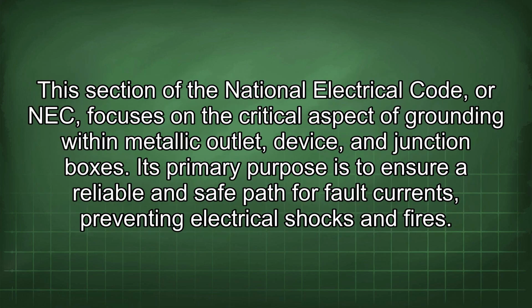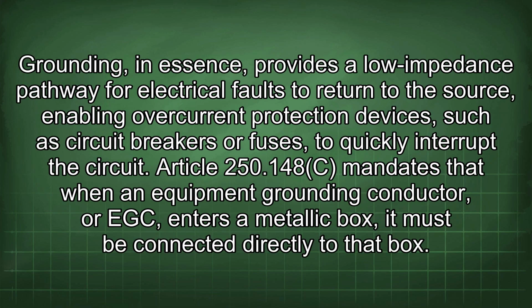250.148c. This section of the National Electrical Code, or NEC, focuses on the critical aspect of grounding within metallic outlet, device, and junction boxes. Its primary purpose is to ensure a reliable and safe path for fault currents, preventing electrical shocks and fires. Grounding, in essence, provides a low impedance pathway for electrical faults to return to the source, enabling overcurrent protection devices such as circuit breakers or fuses to quickly interrupt the circuit.